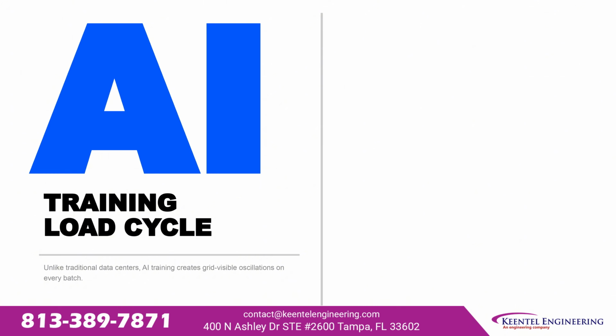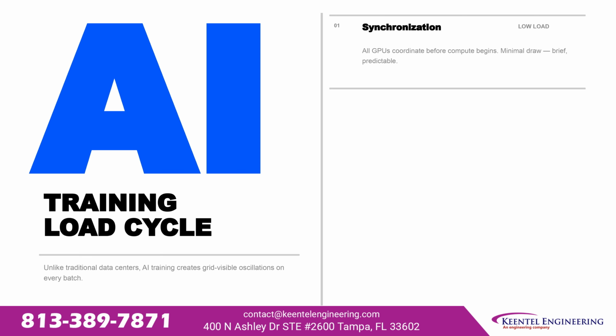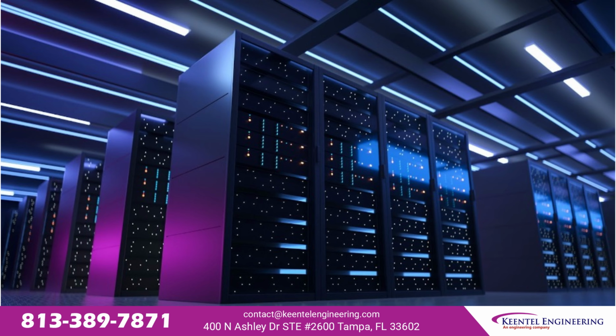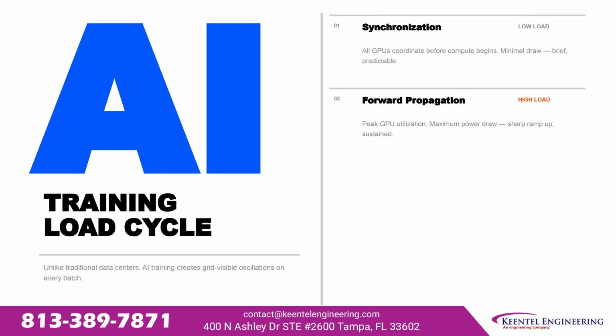AI training creates grid-visible oscillations on every single batch, and the pattern is consistent. Phase 1, synchronization. All GPUs coordinate before compute begins. Load is minimal, brief, and predictable. Phase 2, forward propagation. Peak GPU utilization, maximum power draw, sharp ramp up, then sustained. Phase 3, reconfiguration. Weight redistribution across nodes. Load becomes oscillating and unpredictable.